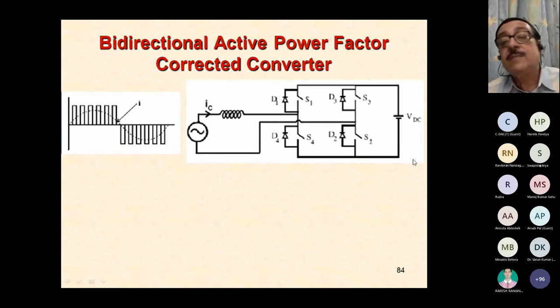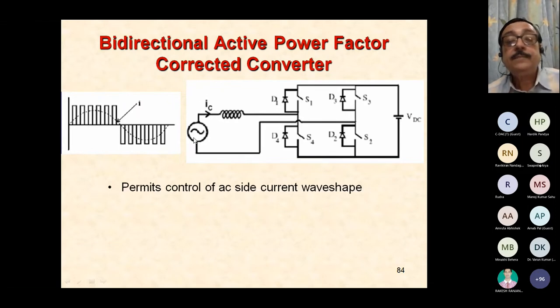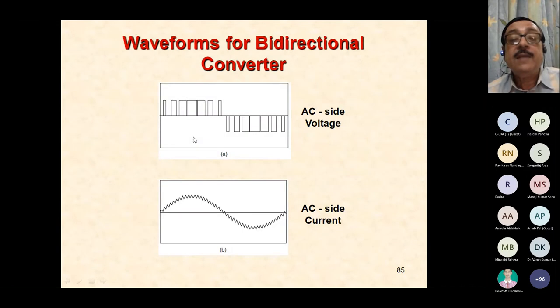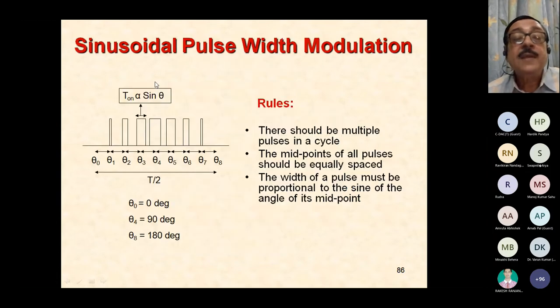So you can have a solar system on this side and this is your grid. So from the solar system, you can feed power back into the grid. You can see the controls are usually sinusoidal PWM type. So the AC side voltage will look something like this, and the AC side current will appear like this, a zigzag type of current. Sinusoidal pulse width modulation, I don't have to explain.